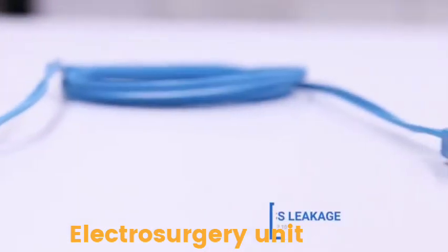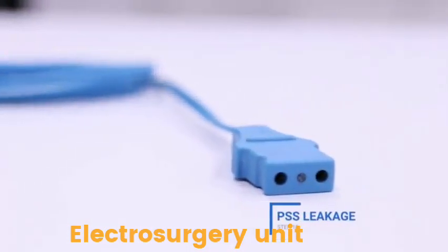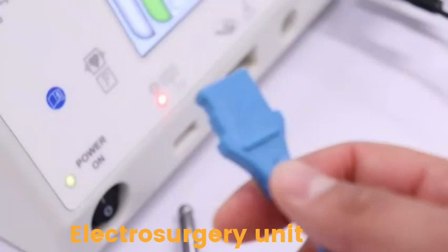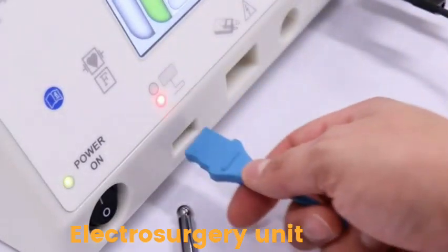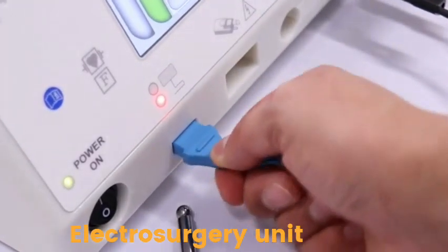To measure pad safe system leakage, use the specialized test cord. Plug the neutral electrode test cord into the PSS receptacle on the GI4000.